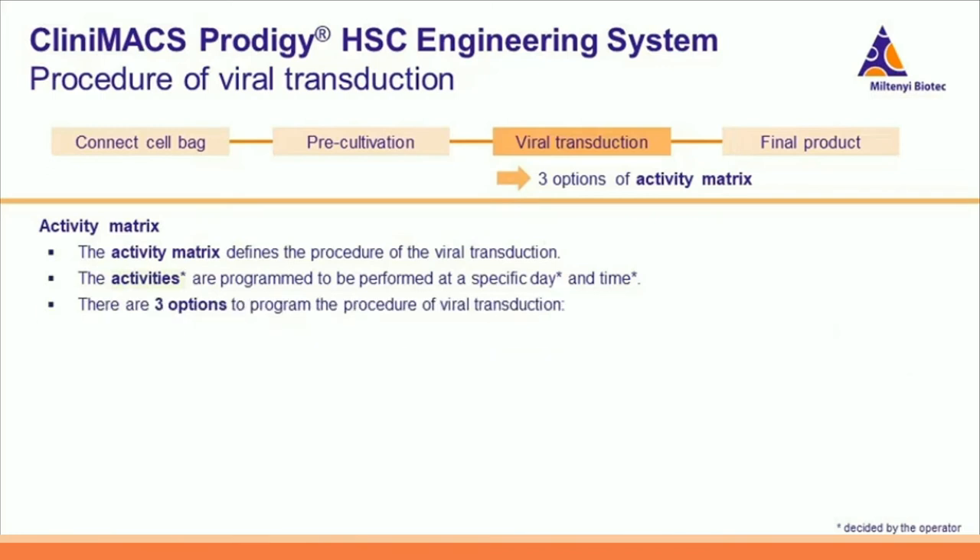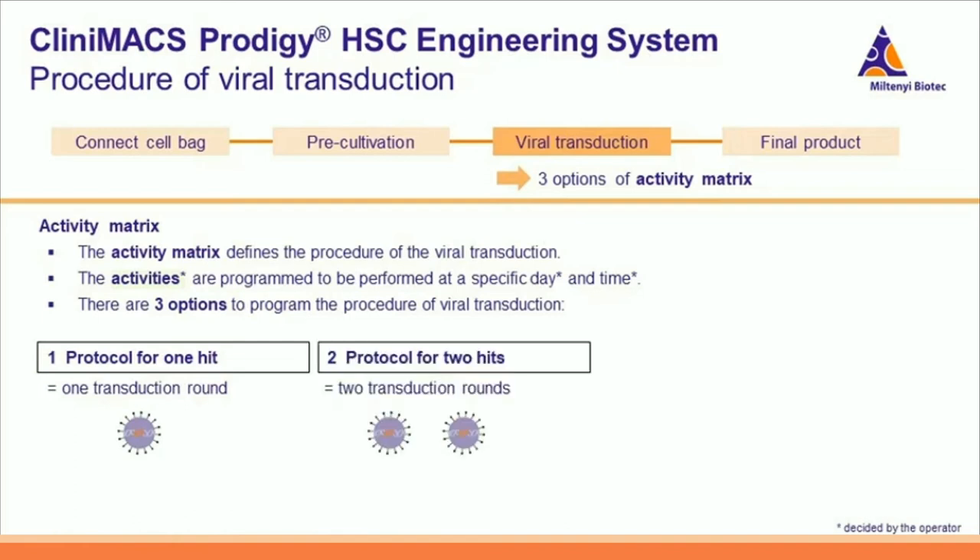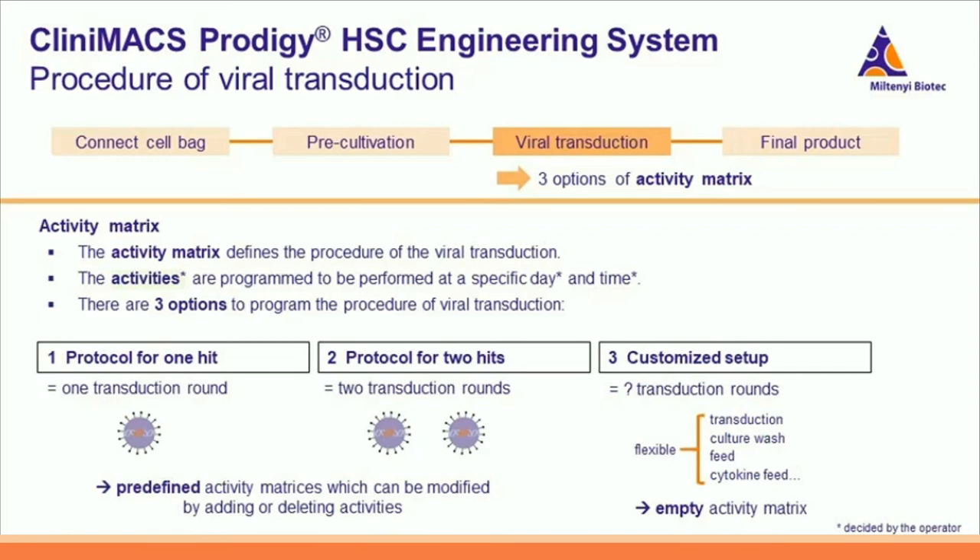There are three options of activity matrices for the HSC engineering process. The 'protocol for one hit' is the predefined activity matrix for one transduction round with a process time of two days — a good starting point if you have a stable and effective viral vector. The 'protocol for two hits' is the predefined activity matrix for two transduction rounds with a process time of three days; the second transduction round may increase transduction efficiency. These two predefined activity matrices are standardized protocols that can be modified by adding or deleting activities. The third option is a customized setup — an empty activity matrix to prepare an individual viral transduction procedure from the start.